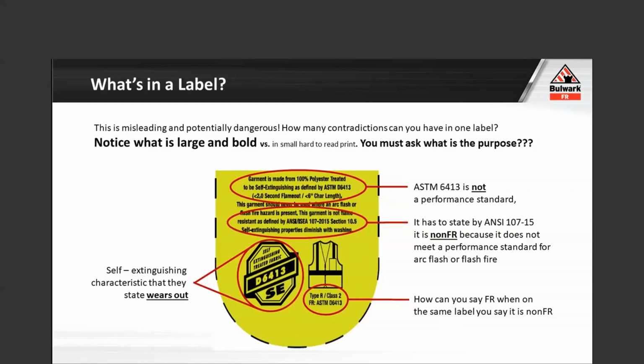Self-extinguishing per ASTM 6413. This is an example of just one standard claiming for it to be FR. On the lower left, you'll see that they created their own terminology, self-extinguishing, as in SE. Even though that's what the test does, there is no adoption of the term self-extinguishing in our particular space in the marketplace for flame-resistant arc-rated PPE. Yes, it's an attribute of the actual test, but there's no adoption of SE as far as it carrying any weight. So it's not a performance standard. It's not one of the standards that is allowed by ANSI 107-15. It has correctly named itself as non-FR, which is a requirement, thankfully, of ANSI 107-15. But then if you read on the lower right, it goes back to claiming that it's FR. So is it non-FR or is it FR? That is a lot of misinformation on one label.